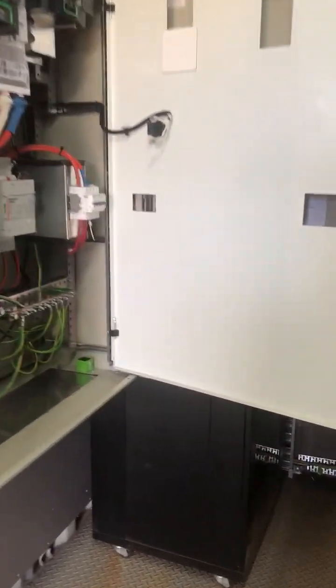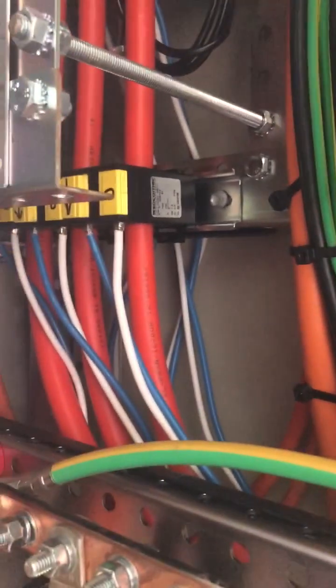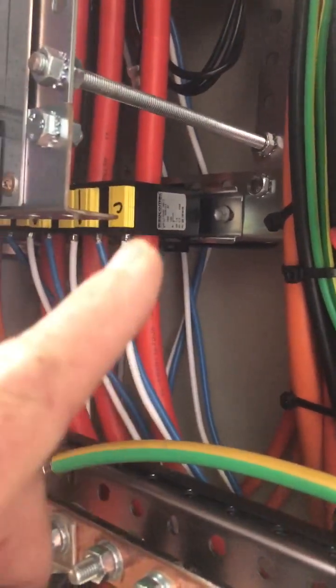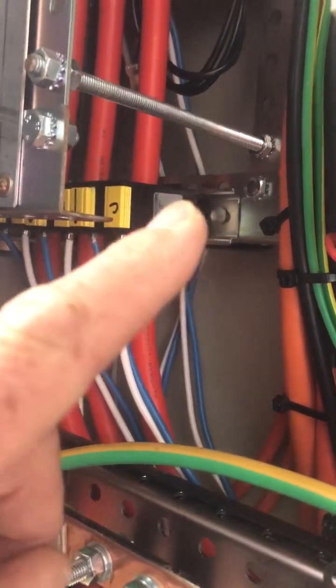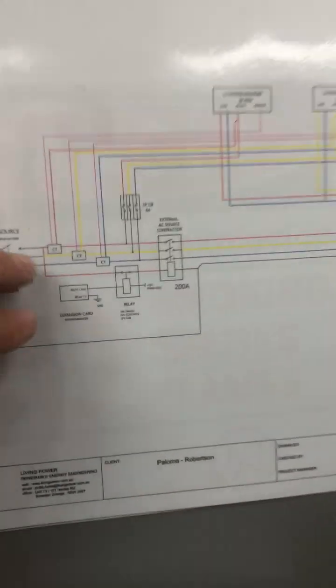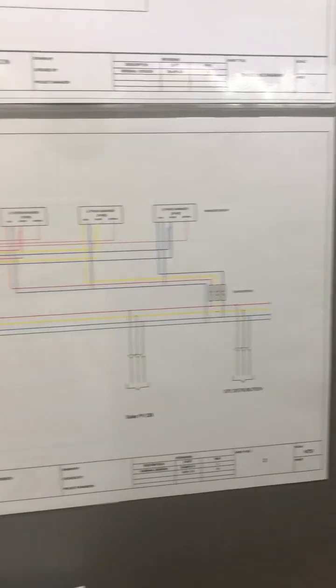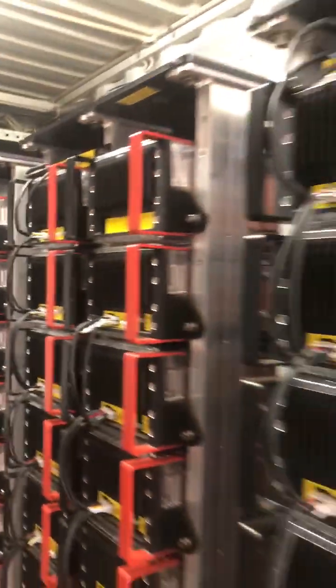And so I mentioned CTs a minute ago. If you look carefully in under the switchboard, you see those little yellow things there. That's the current transformers, the CTs, and they're measuring the current coming to and from the generator, and that's them there. So a well-constructed single line diagram like that can be very useful to someone coming to a site who needs to understand what's actually going on here.